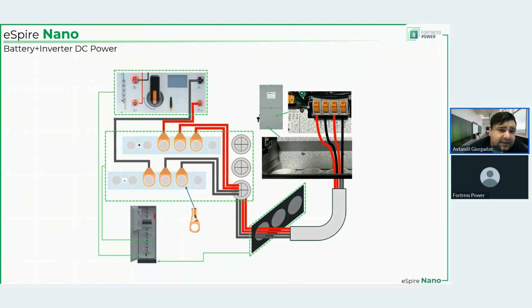Obviously, this negative and this positive is connected to the battery module right above the battery management unit. Now, positive and negative cables go through this rubberized inlet, and if you count left to right, the first conduit knockout, this is the conduit that is included. This goes to the inverter, and you connect to inverter battery pluses and battery minuses. And this is how the primary, or 1 battery, connects to its inverter.